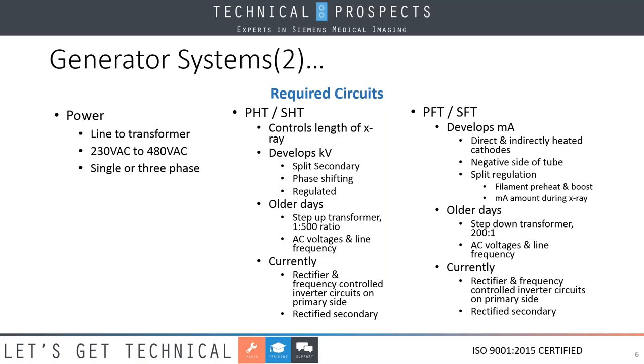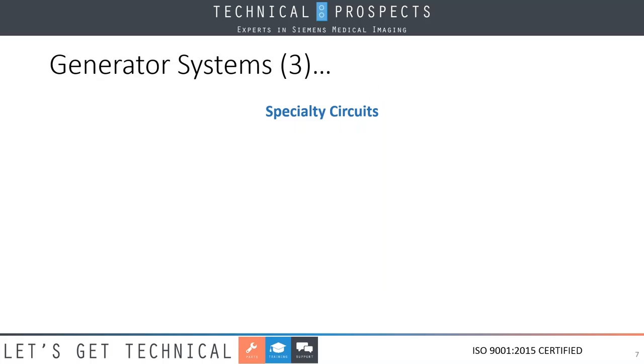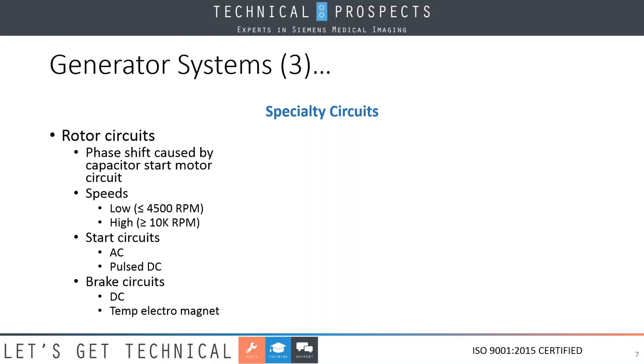So as you can see, we have five required circuits. Now, there are some optional circuits here, or specialty circuits, as I call them. The first one we're going to look at is the rotor circuit. And this is strictly there if you have a rotating anode on your X-ray tube. Some old dental systems do not have that, and therefore you won't find a rotor circuit there. So that's why I call this a specialty circuit.